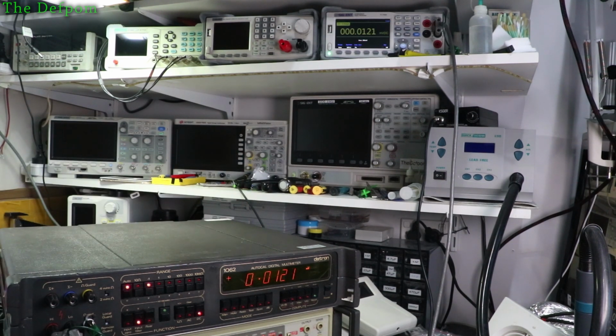I was going to go up in, I don't know, let's do 1 microvolt. You can see they're very similar numbers there. 10 millivolts. Okay, they're kind of tracking, right? They're very similar. I've got very low signal levels here, so a bit of noise will affect the numbers a little bit. So 100 millivolts. We're getting a little bit of an error here. I've got a 20 count error. I'm still getting a 20 count thing on here somewhere. I'm not sure it's an issue or not.